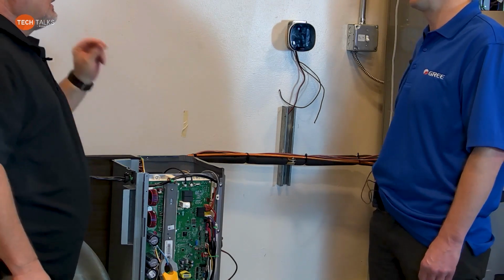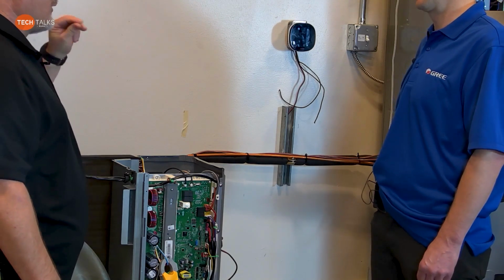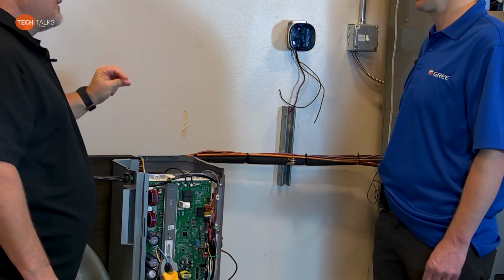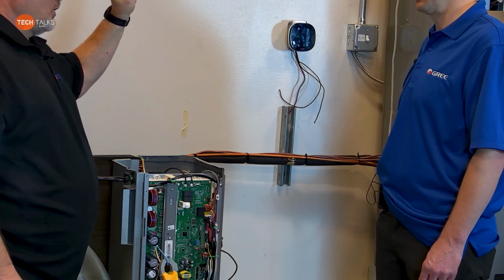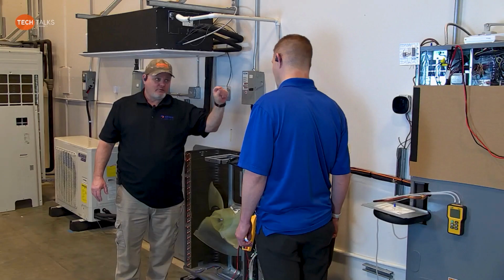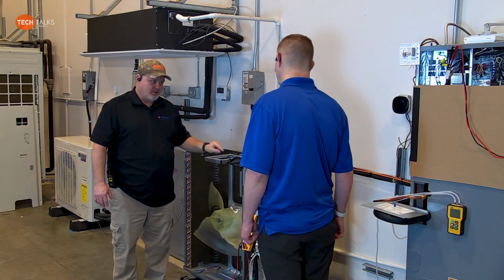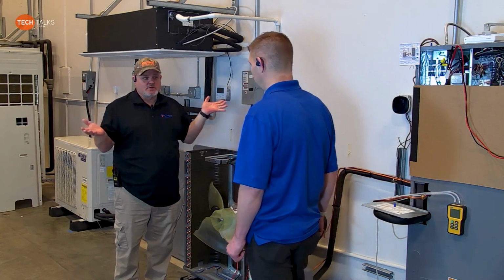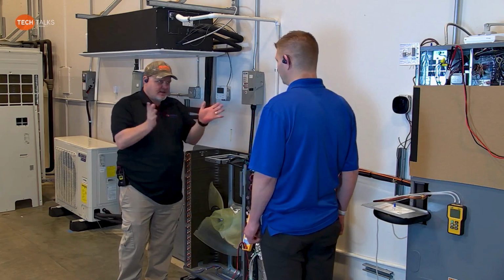And the indoor, correct. And then I'm assuming if we go to RS485, we have to have dip switch number 1 on SA1 off on the air handler and off on the outdoor unit. That is correct. Okay, cool. So that's pretty easy to remember. Yep. So that's not that complicated.